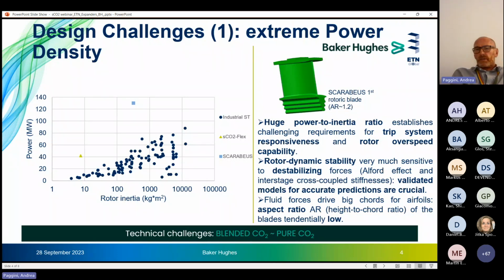There are also further design challenges which are indirectly or broadly correlated to the huge power density. I would mention rotor dynamics and flow path mechanical design. For rotor dynamics, these kinds of machines are very sensitive to the destabilizing forces coming from the flow path design. So the rotor dynamic stability is very much affected by these destabilizing forces. I'm referring to the Alford effect and to the interstage cross-coupled stiffnesses, which are typically the major sources of destabilizing actions. So it's extremely important to have accurate and validated models in order to have a reliable prediction of the rotor dynamic behavior of this machine.